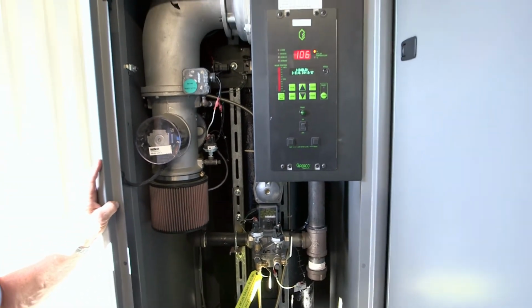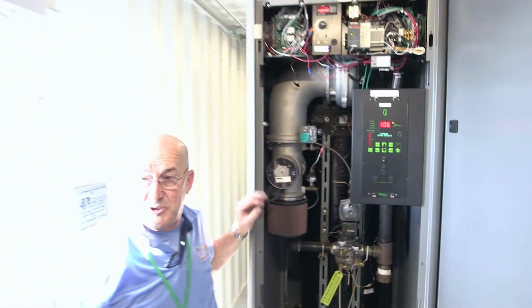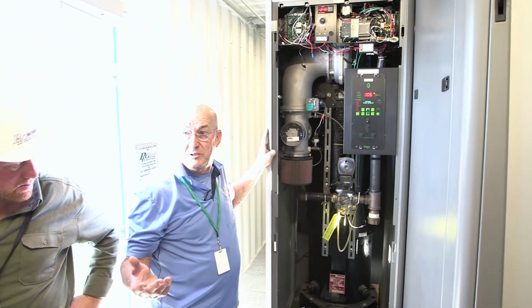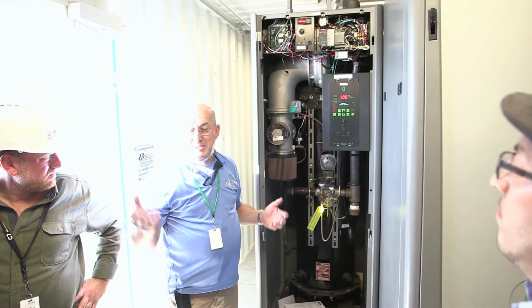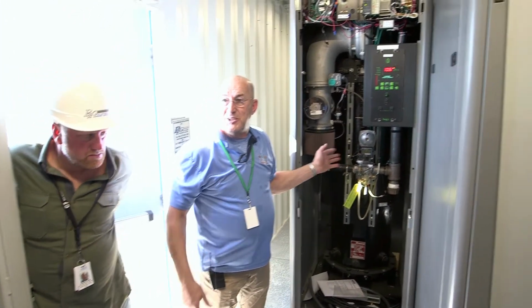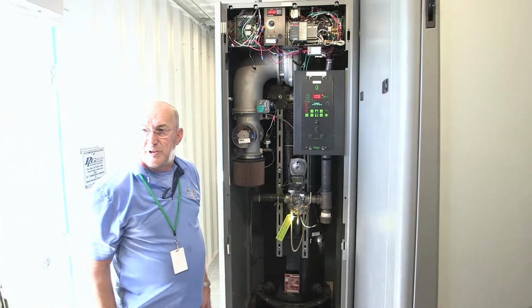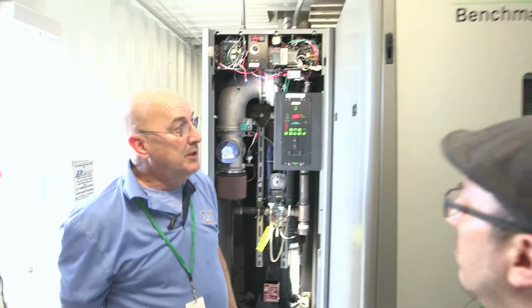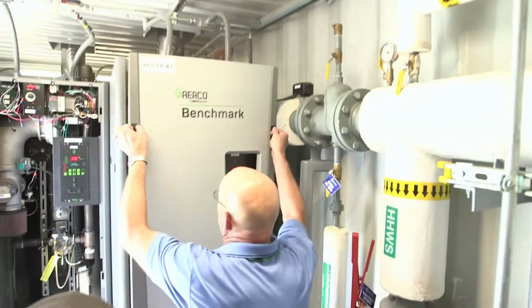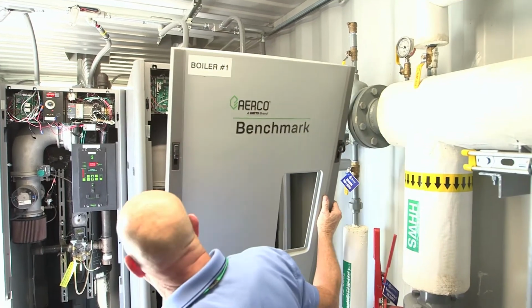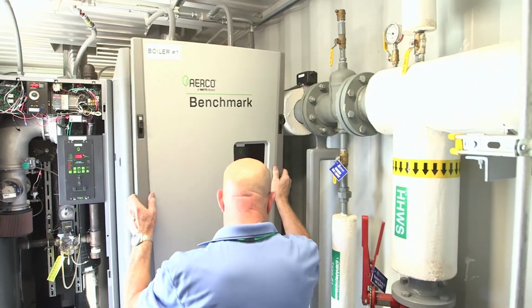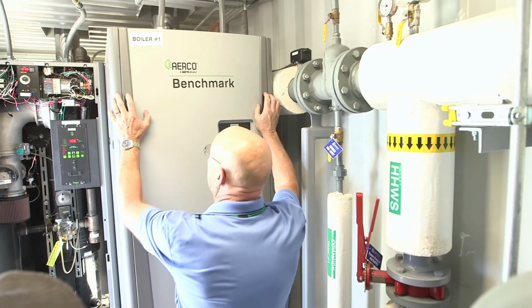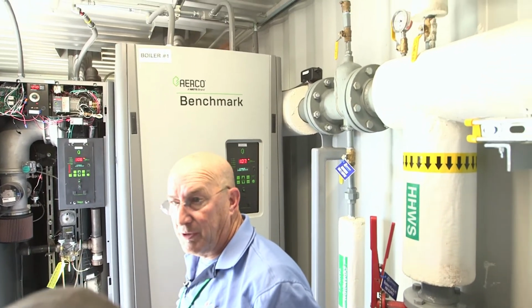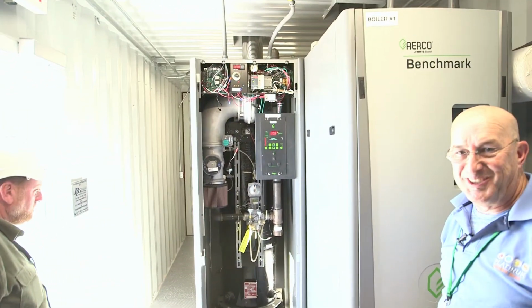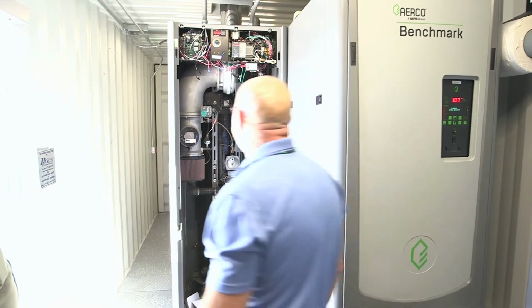But in the beginning, you don't know what kind of debris you have in the air here. It may have to be done twice a year, may have to be done three times a year, depending. You're on the water. It gets windy, kicks up a lot of sand, you never know. So there's no harm in just looking at it to see what it looks like and make sure it's okay. The cover comes off very easily. You just pull the handles and you get right in there. You put the cover back and you lock them down. It's not rocket science, it's easy. Everybody likes easy. All right?